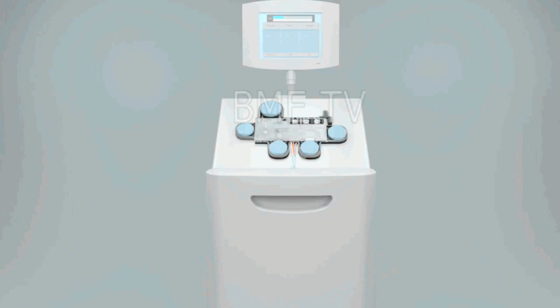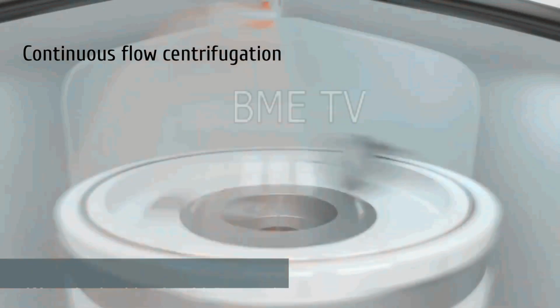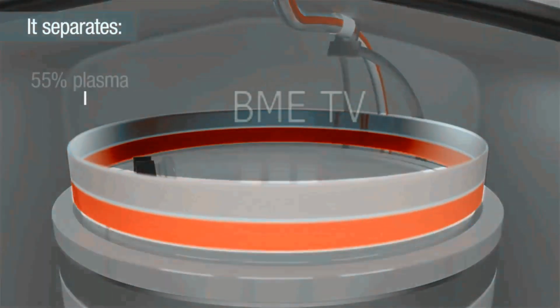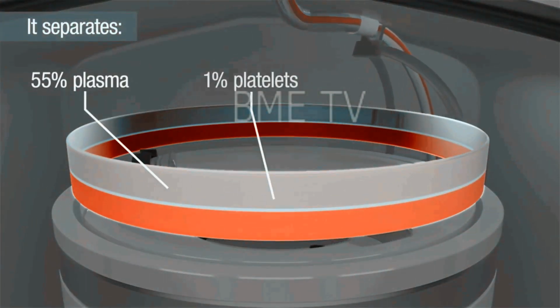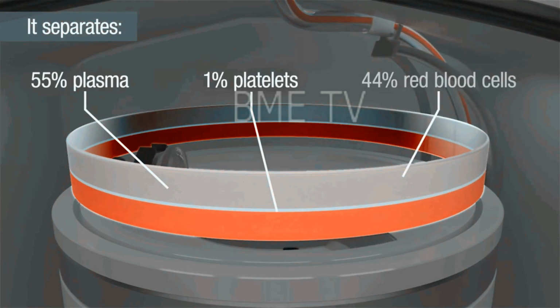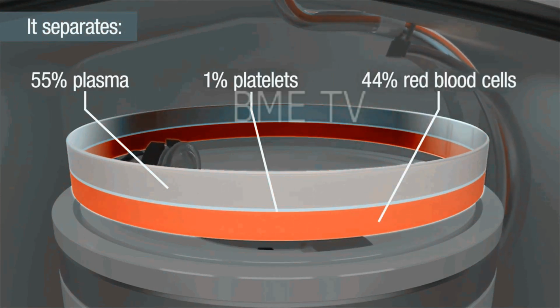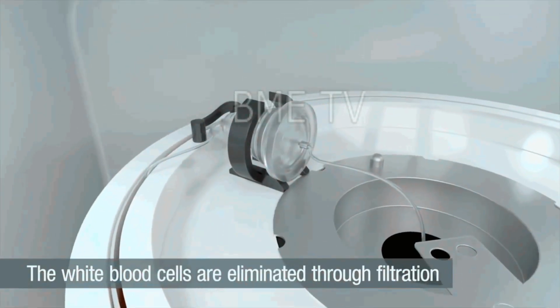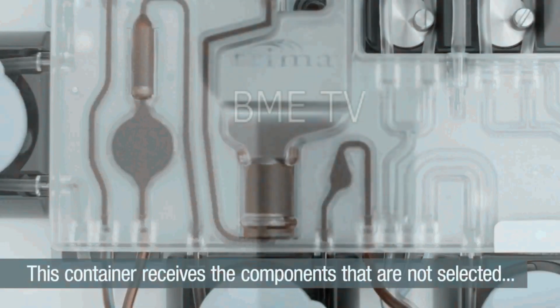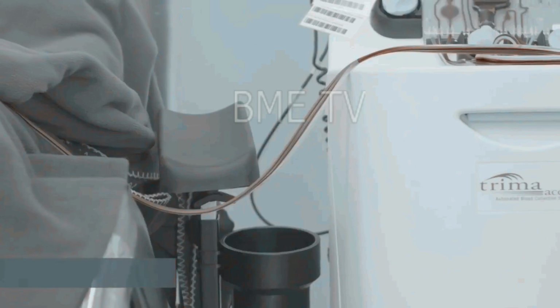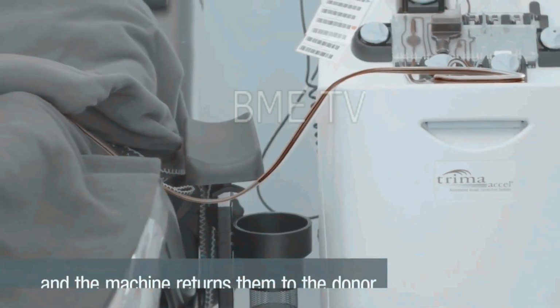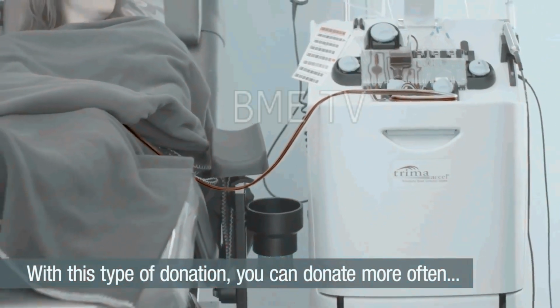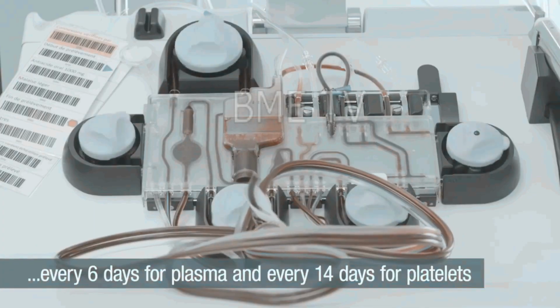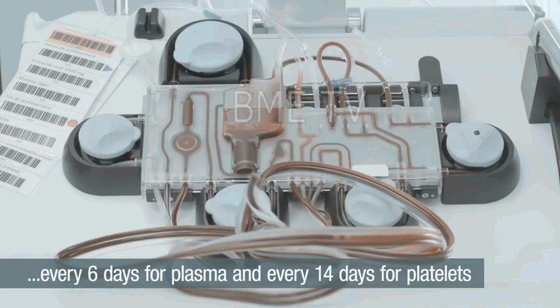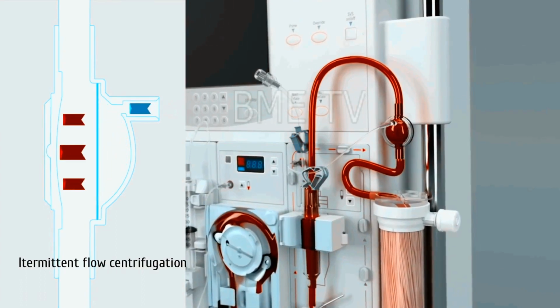The centrifugation method can be divided into 2 basic categories. The first method is continuous flow centrifugation. Continuous flow centrifugation, or CFC, historically required 2 venipunctures, as the continuous means the blood is collected, spun, and returned simultaneously. Newer systems can use a single venipuncture. The main advantage of this system is the low extracorporeal volume, calculated by volume of the apheresis chamber, the donor's hematocrit, and total blood volume of the donor used in the procedure, which may be advantageous in the elderly and for children.